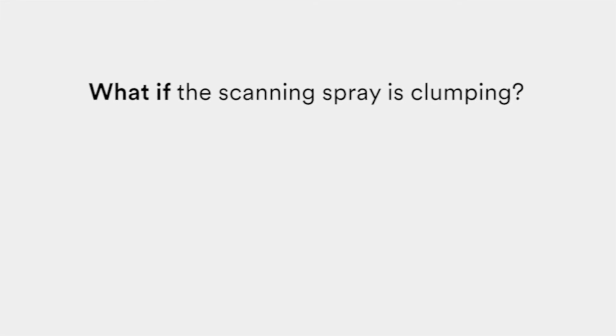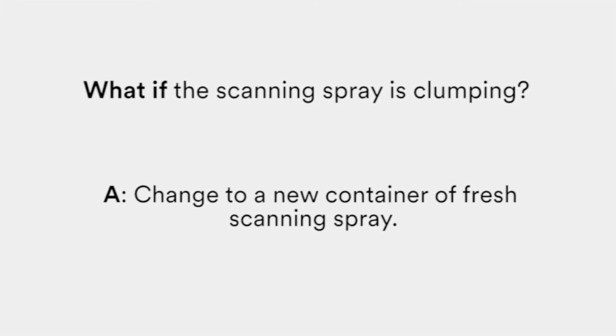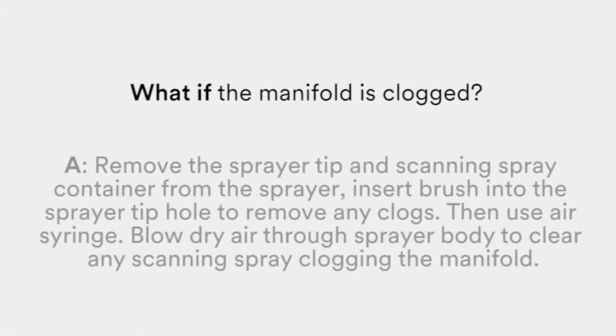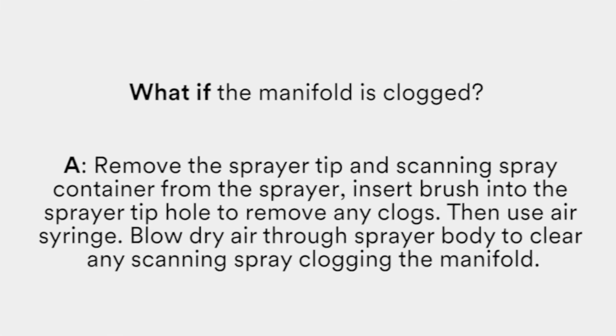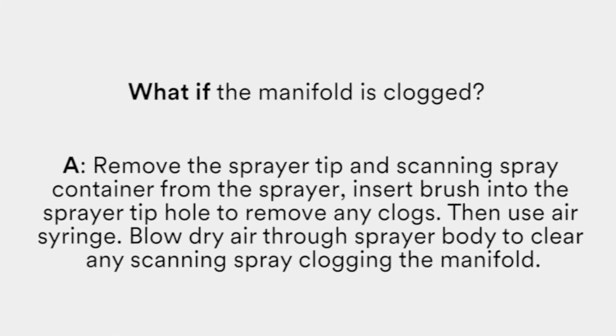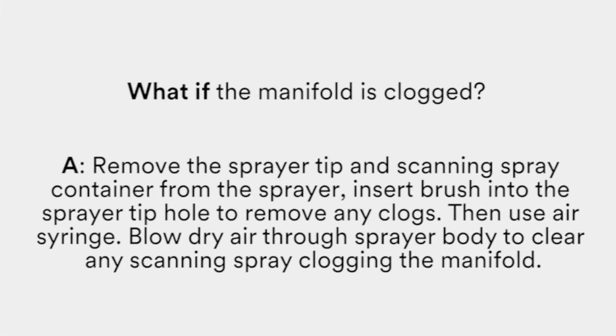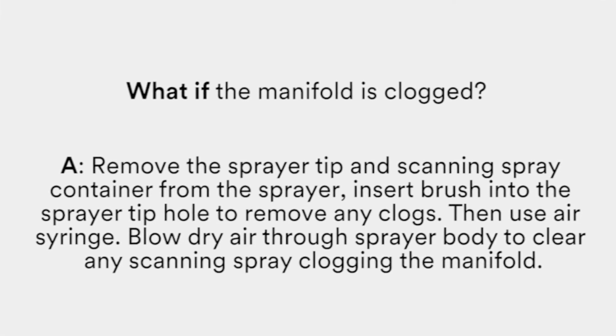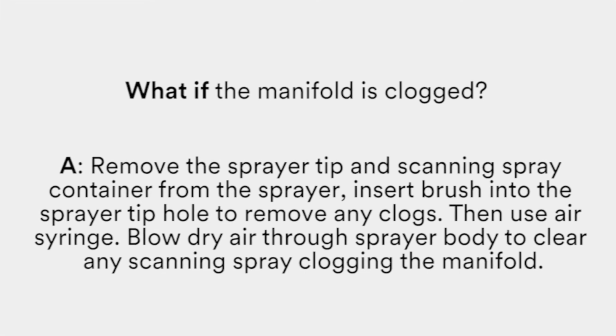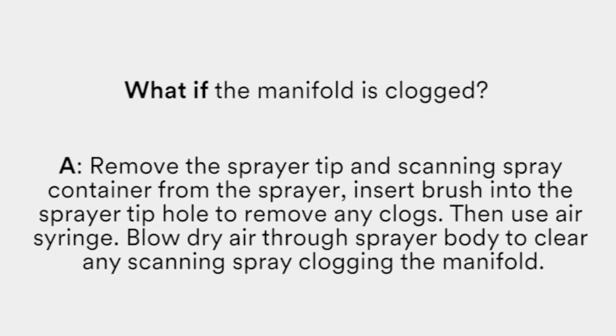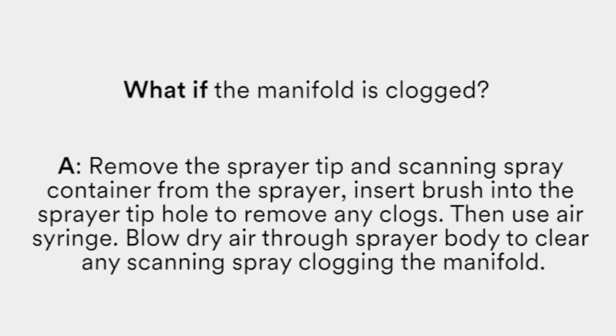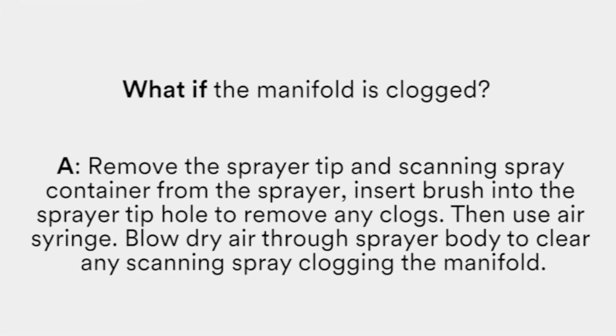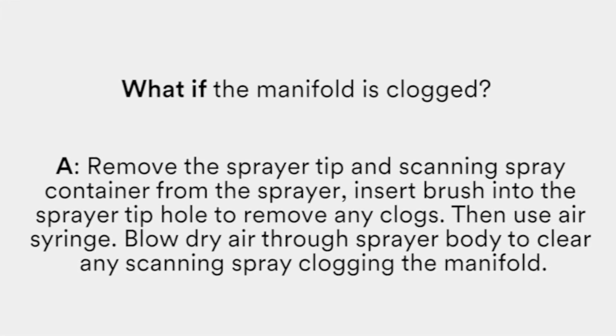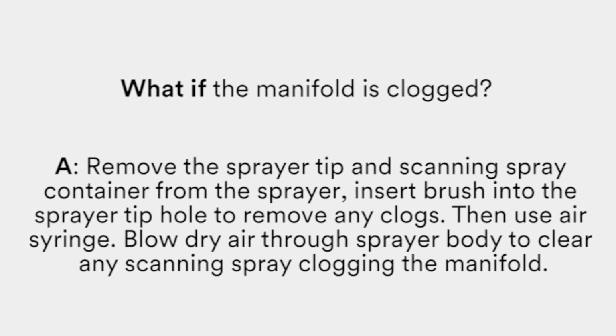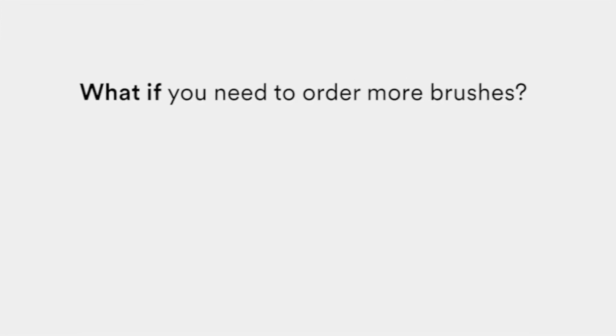What if the scanning spray is clumping? Change to a new container of fresh scanning spray. What if the manifold is clogged? In this case, remove the sprayer tip and scanning spray container from the sprayer. Insert the brush into the hole that holds the sprayer tip to first remove any clogs. Then use an air syringe. Blow dry air through the sprayer body to clear any scanning spray clogging the manifold. You will also use the brushes to remove any excess scanning spray in the sprayer tip and/or replace with the new disinfected sprayer tip. What if you need to order more brushes?